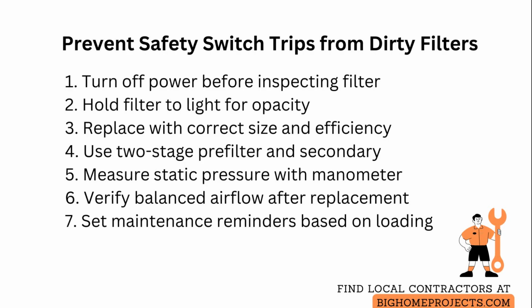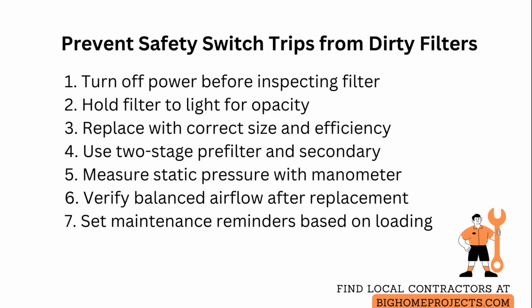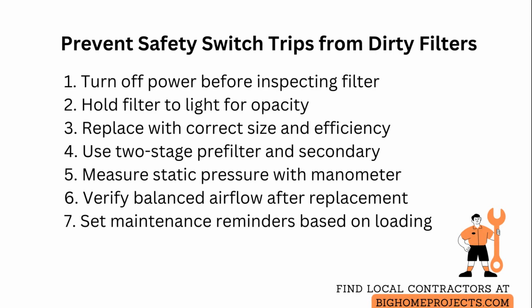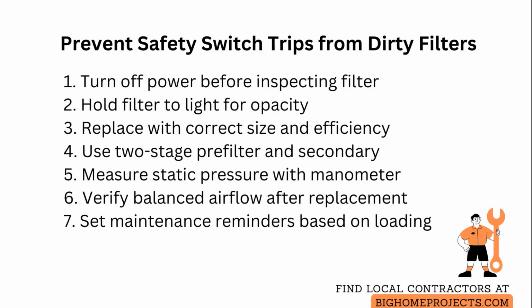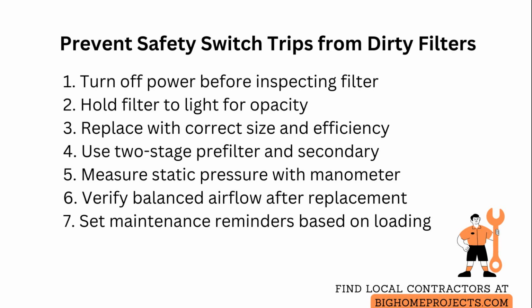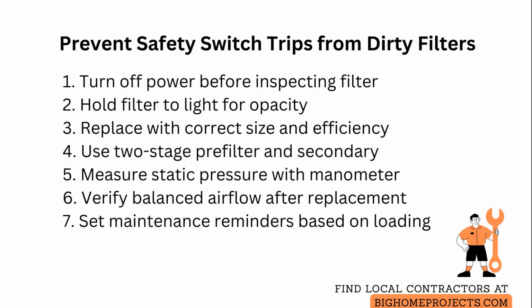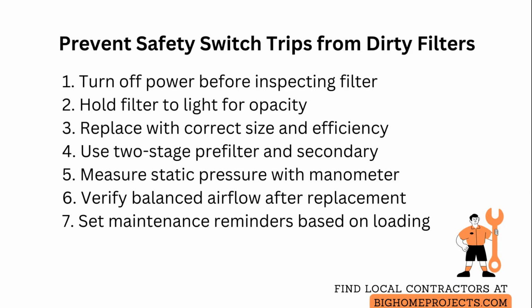Start by turning off power and inspecting the filter box and return plenum for dust, pet hair, and insulation fragments. Then slide the filter out and hold it to a light source to check for opacity as a quick field test. Replace filters with the correct size and minimum efficiency as specified on the equipment data plate, and avoid using an oversized or overly dense filter that will itself reduce airflow.